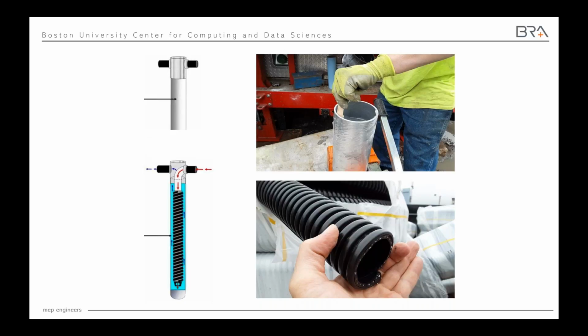That's the EPDM material, so it's a more insulating material. And the water goes down the inner pipe and then it comes out into the outer pipe and on its way back up, and that's where it's a thinner walled system. It's exchanging with the ground, so you get higher performance out of that.